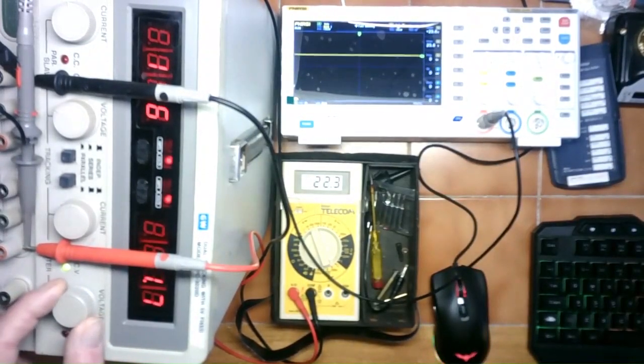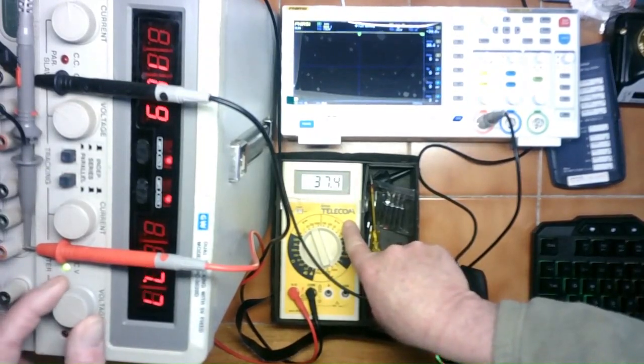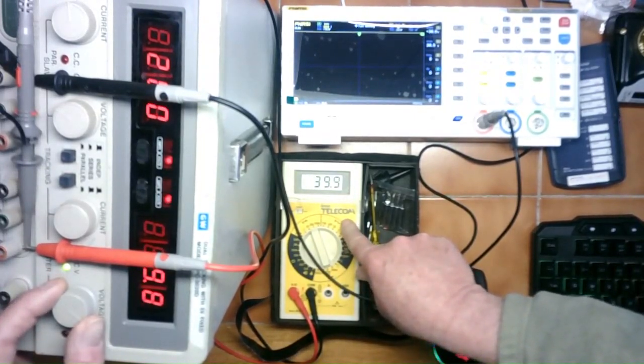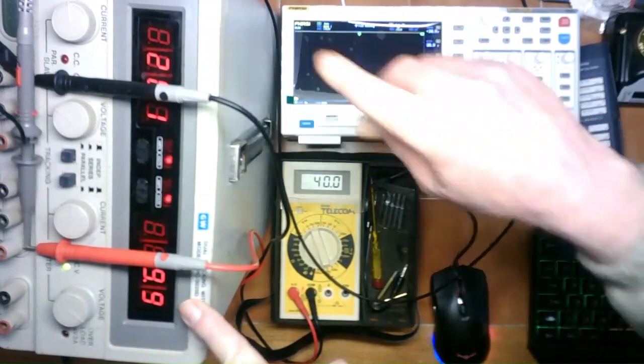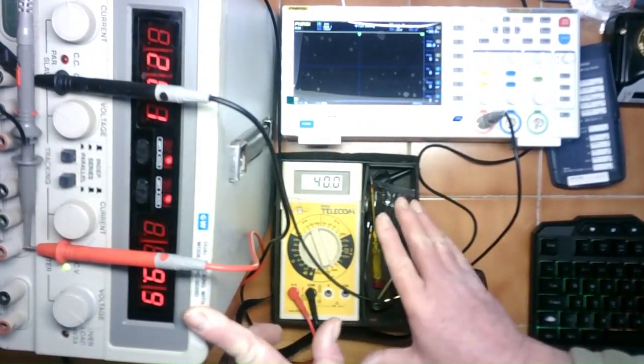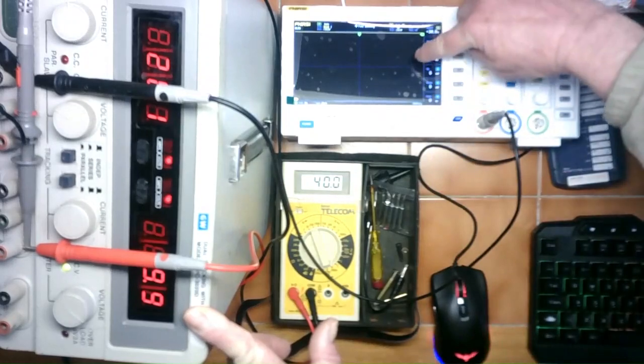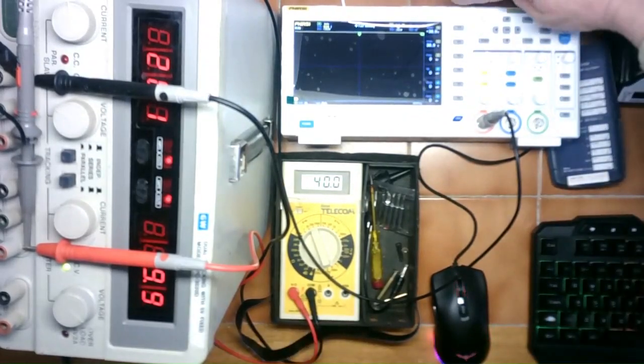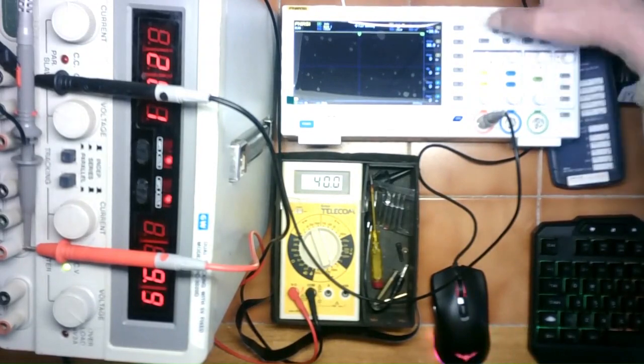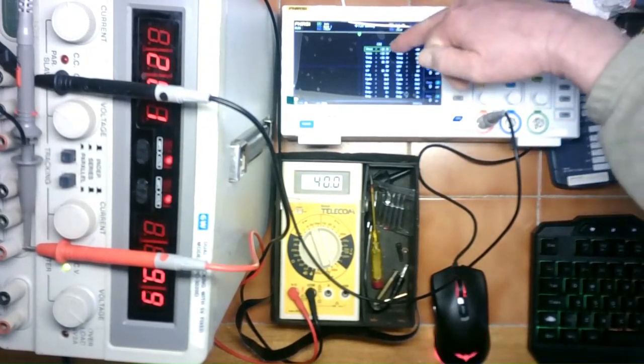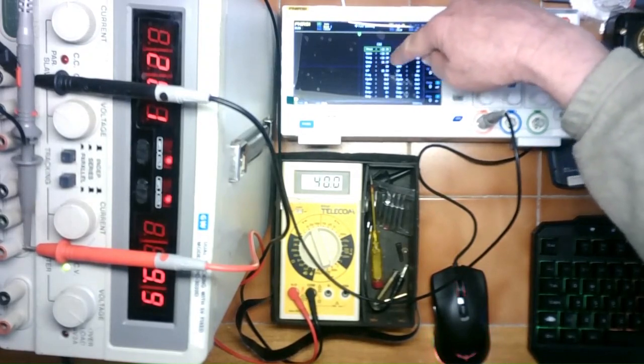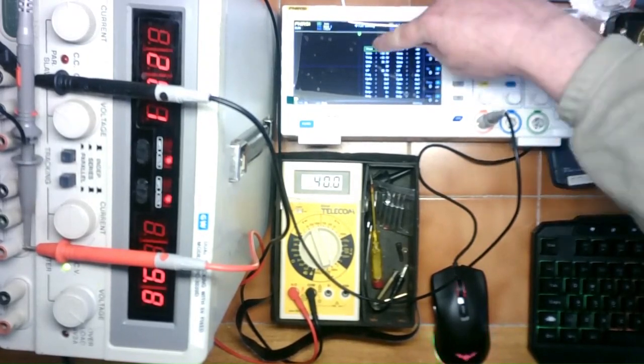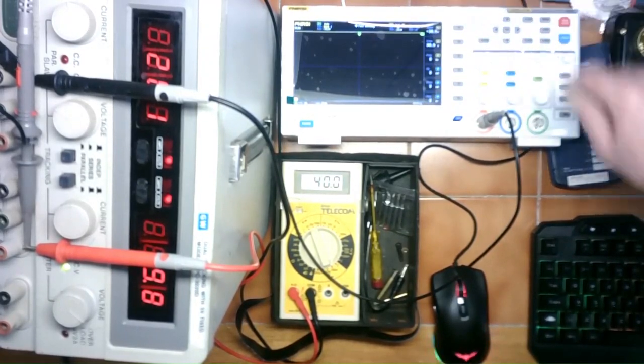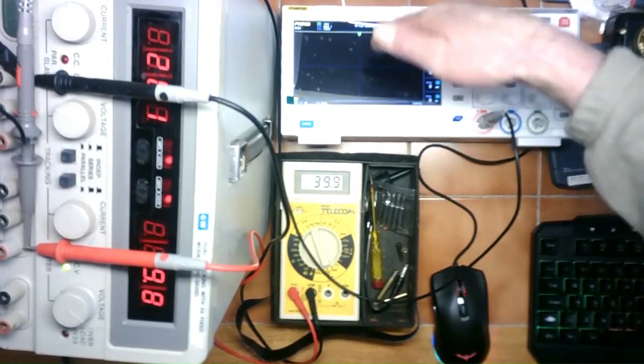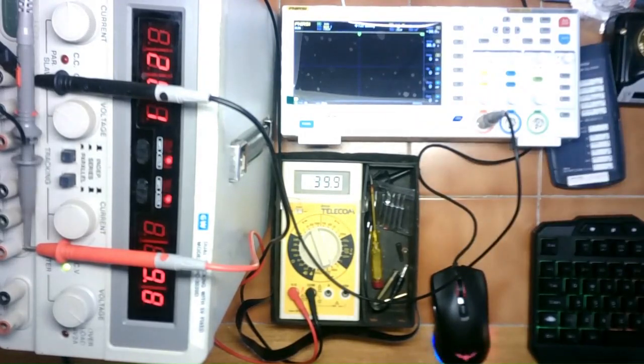So winding that back up to get exactly 40 volts on the meter, which is there. Again, I've got the 20.1 on one side, 19.9 on the other side. So I'm going to take it as the reference of 40 volts. This has now hit the top of the screen, and that's its limit. Unfortunately, the actual maximum voltage, which you can set your parameters here, what you want to read, you can set Vmax or VRMS and voltage peak to peak, etc. This is set to Vmax, and it's reading 38.9 volts when it's hit the top of the scale. And it's supposed to be a 40 volt input.